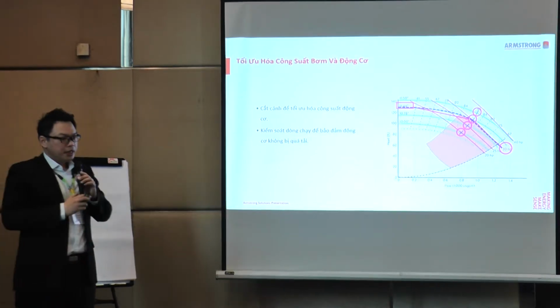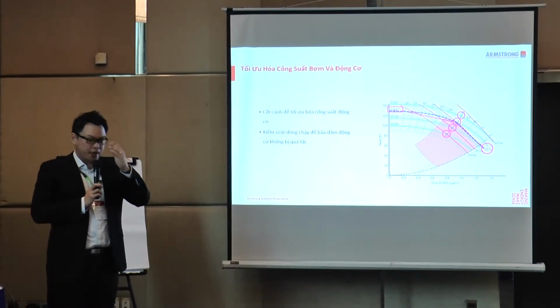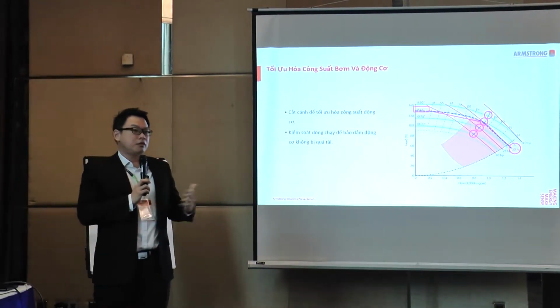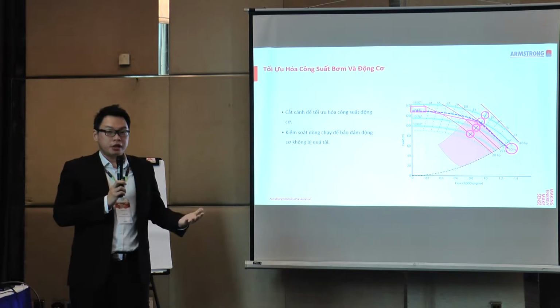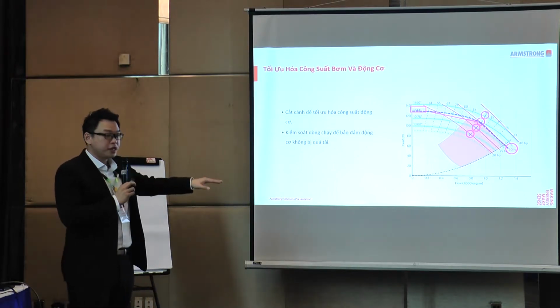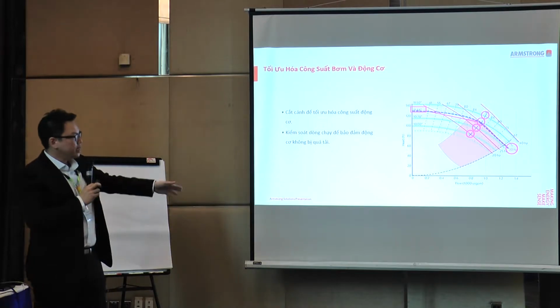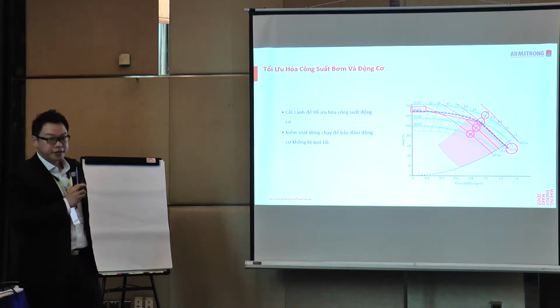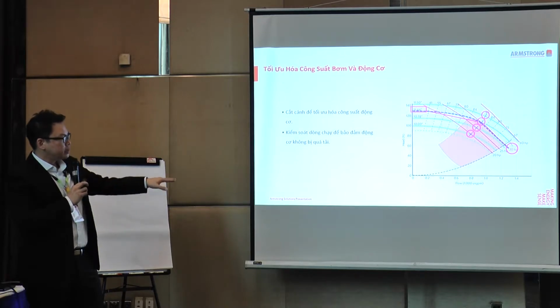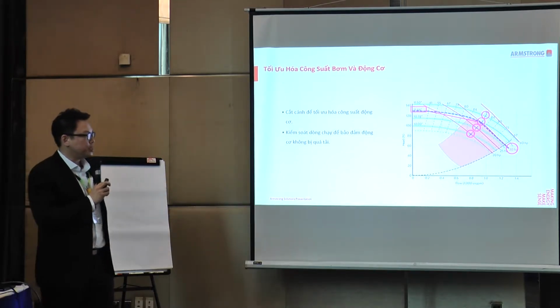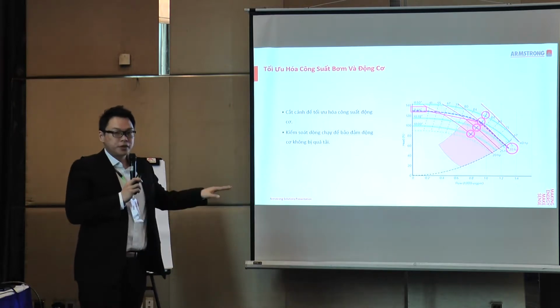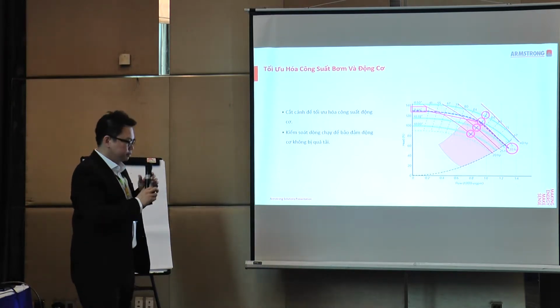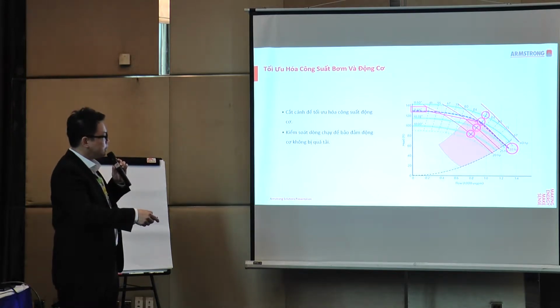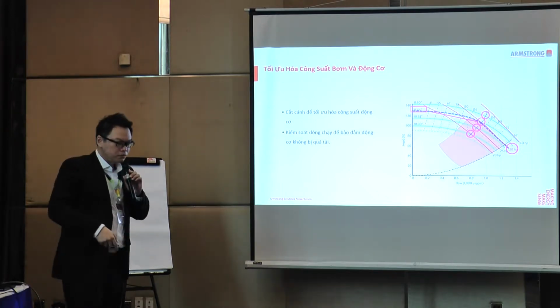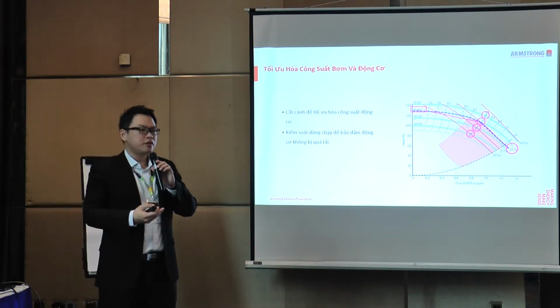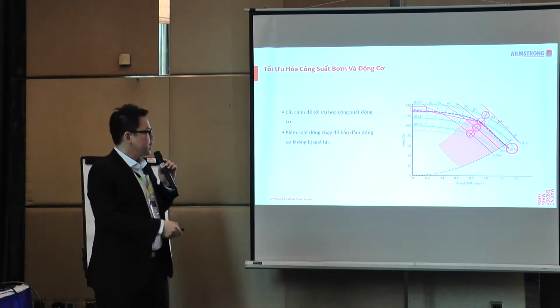Okay, next. This is something you may find a bit interesting, because I believe not all manufacturers use this approach. If you can follow along, on the y-axis, maybe I'll choose a point, 90 feet of head, and on the x-axis, I'll put 900 GPM. If you follow along this graph, you get to this spot here.